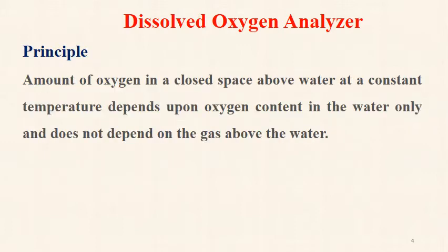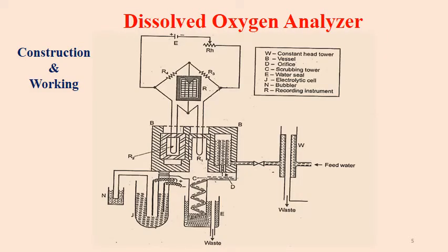The principle behind the dissolved oxygen analyzer is that the amount of oxygen in a closed space above the water level at a constant temperature depends upon oxygen content in the water only and does not depend on the gas above the water. So, the measure of oxygen above the water level is the measure of dissolved oxygen in water. Let's see about the construction and working of dissolved oxygen analyzer.